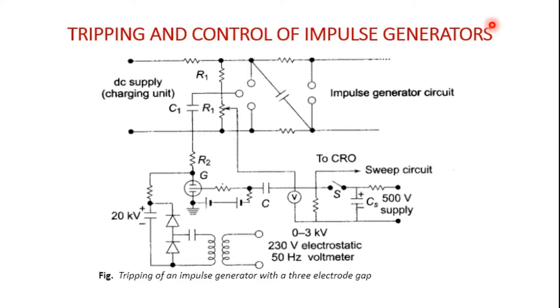To trip the generator at a particular predetermined time, the spark gaps may be mounted on a mobile frame by reducing the distance by moving one electrode closer to the other, creating the possibility of conduction between the two. However, this method is difficult and does not ensure consistency in control, so a simpler method uses the three electrode gap arrangement, as seen in the generator circuit.